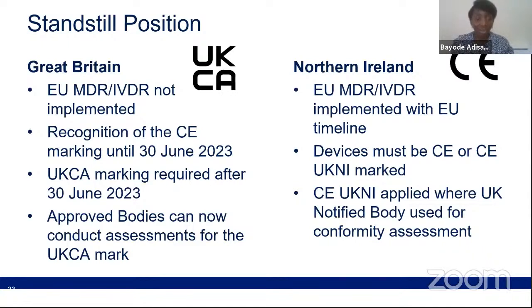So back to Great Britain. The MHRA will continue to recognise CE marking until the 30th of June 2023. However, from the 1st of July 2023, a UK CA mark will be required in order to place a device on the GB market. And where third-party conformity assessment is required, a UK approved body is needed. Manufacturers at the moment can use the UK CA mark on a voluntary basis until the 30th of June 2023. After that, it will be a legal requirement.